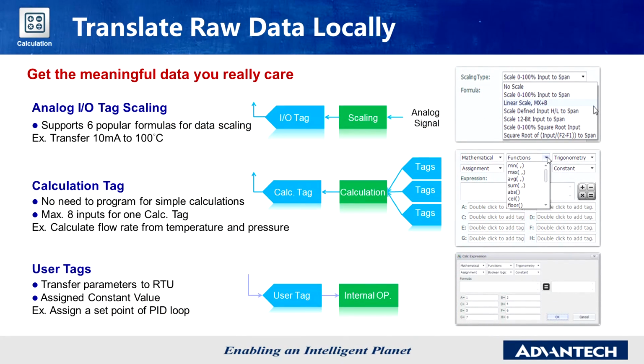Not only analog I/O data scaling, we also provide calculation tags with a very simple configuration tool. Customers can integrate tags into a formula and calculate meaningful values easily. For example, in some applications, the real flow rate is calculated from temperature, pressure, and the difference of pressures—combining these three variables gives a real flow rate easily.